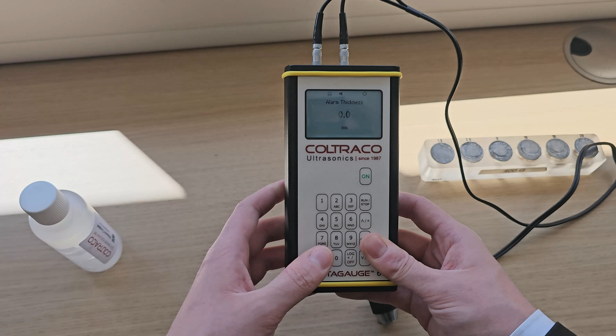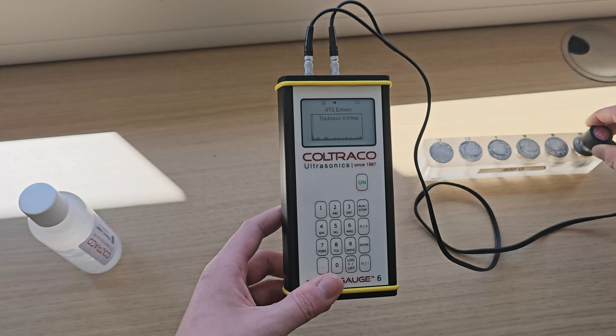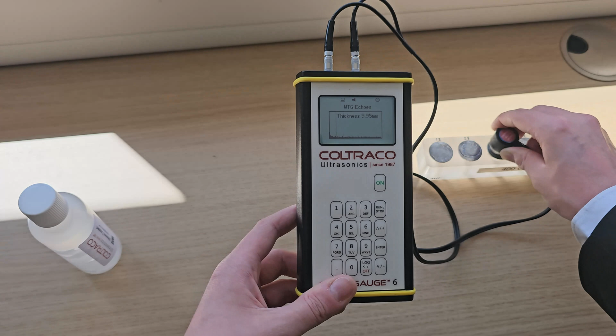you can hear that right now the device is beeping at me, and that's because, as you can see, it's currently reading 0mm. So if I place this once again onto the 20mm block, once it obtains a reading, you will see, there we go, it's obtained a reading and the alarm has stopped. Move down to 15 and you see still no alarm, down to 10, no alarm, 5, and there you go. We're measuring just shy of 5mm here, and you can hear that the alarm has started going off. And again down to 2.5, still got the alarm, 1.5, still an alarm, and then back up to 10.